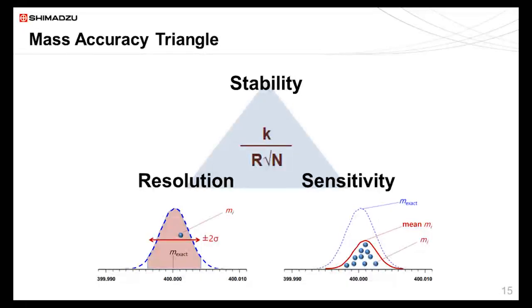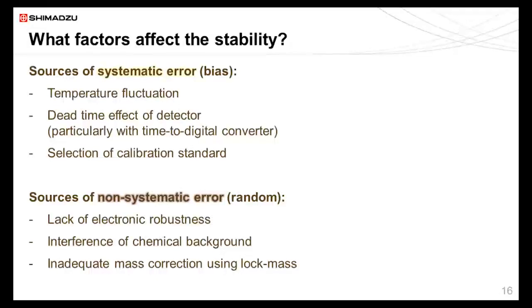So I've shown this relationship in a triangle. What's important in accurate mass measurement are the three factors: resolution, sensitivity, and sitting on top of these, the stability. So I've denoted this relationship as K over R root n. Resolution is important for individual ion measurement, and sensitivity is important because you need to sample a sufficient number of ions to approximate the distribution to the theoretical distribution. So now the important factor again is the stability.